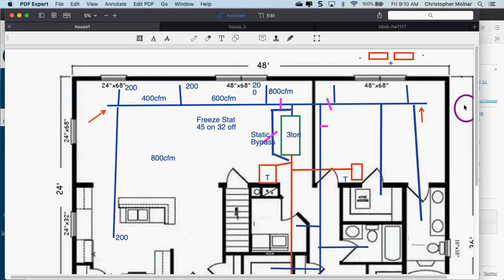The bypass and the thermostat sensor on the outside unit were the things to make sure work properly. The instructor agrees that's the important stuff. The student notes the room came out to about 190 CFM. The instructor responds: if it's 190 CFM and you've decided on a one-and-a-half ton, that is honestly pushing it.